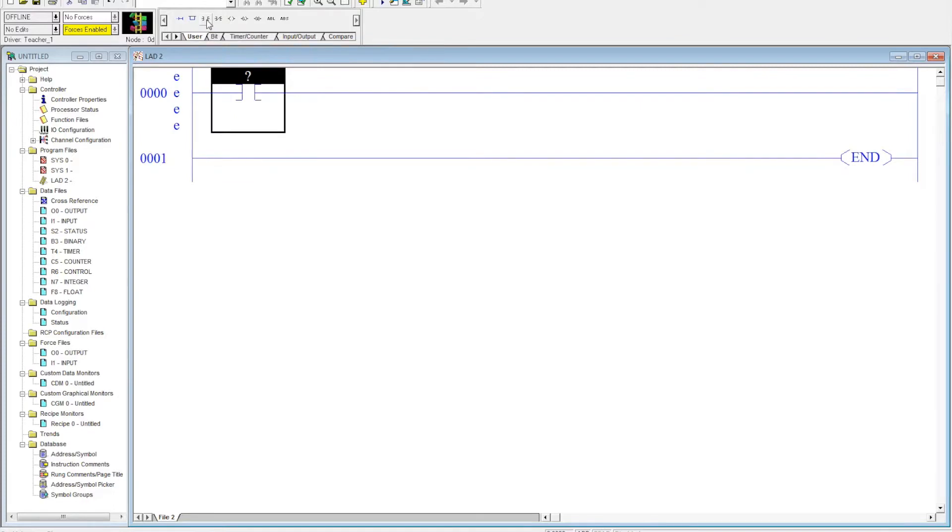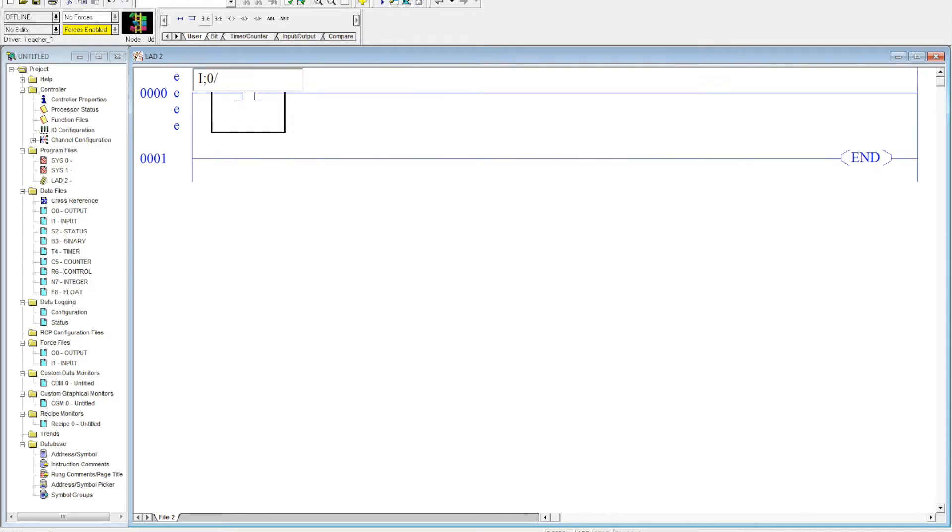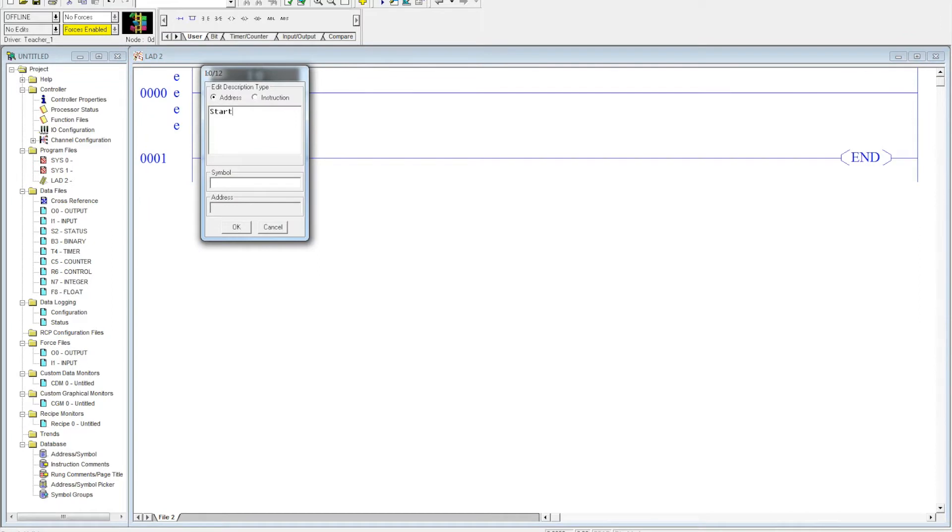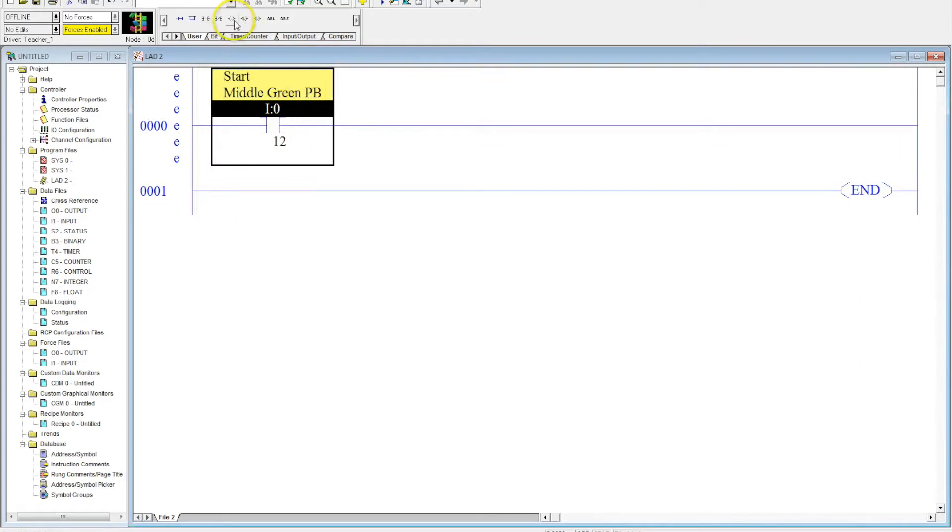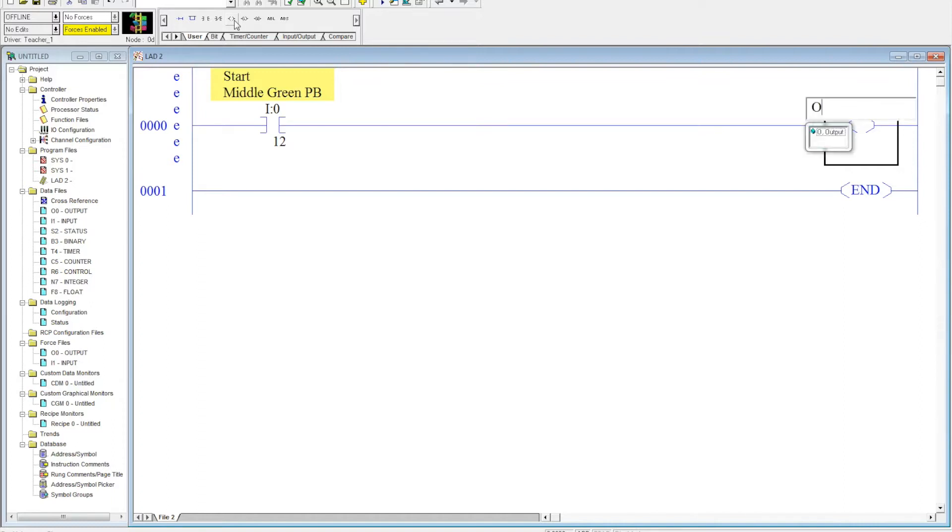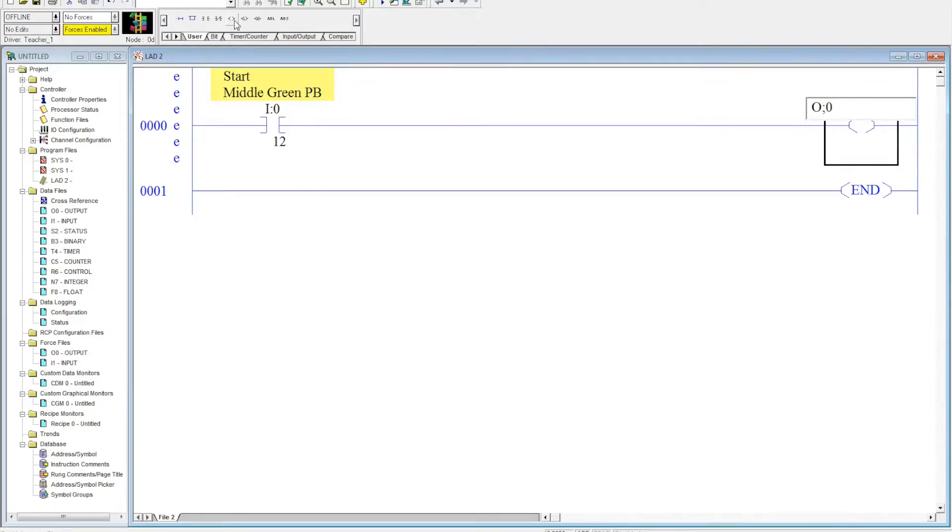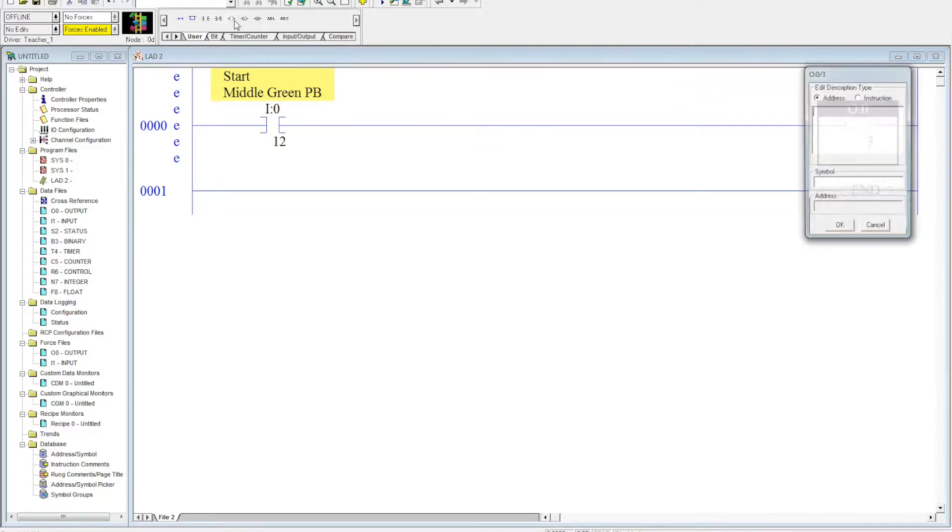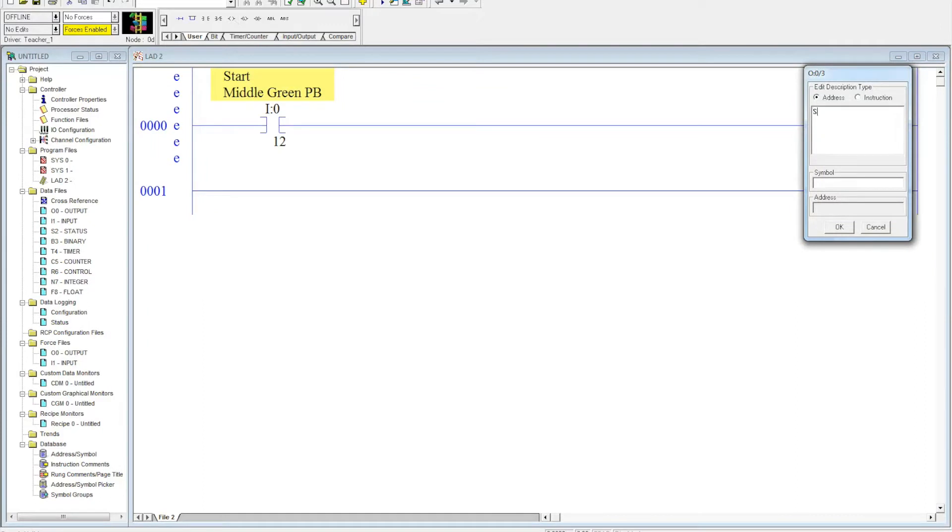So the first thing that we're going to do is we're going to tie in our middle start button. So that was address I colon zero forward slash 12. For the name, we're going to call this start. And this is the middle green push button. Select OK. Name pops up. Then we're going to put our output. Now the output for this is an output that we haven't used so far. So this is output colon zero forward slash three. OK. We hit enter. This is solenoid one. Enter. Now what we're going to do here, and then we hit OK.